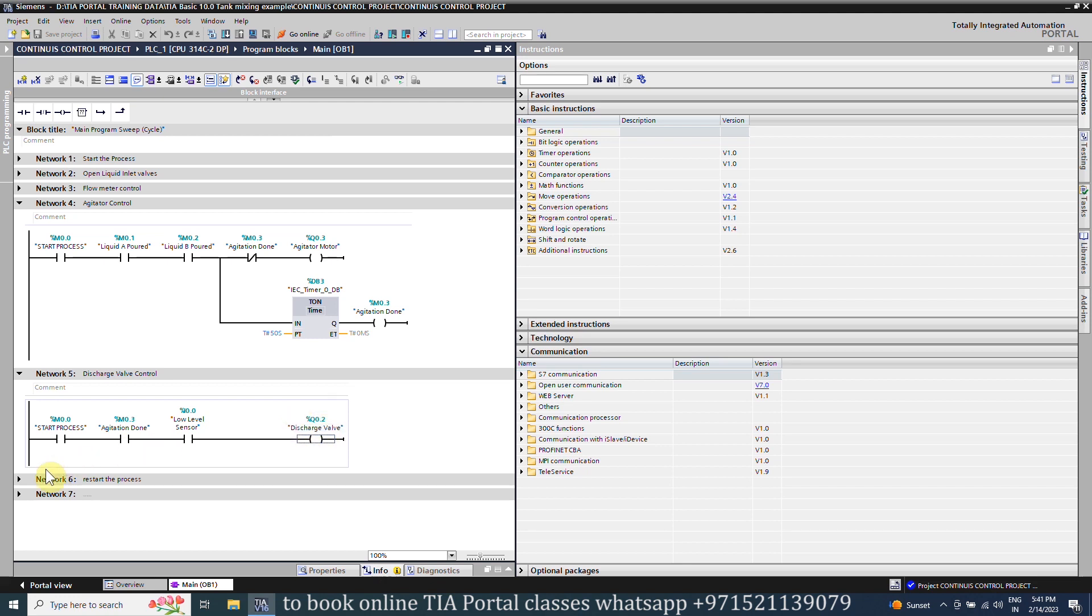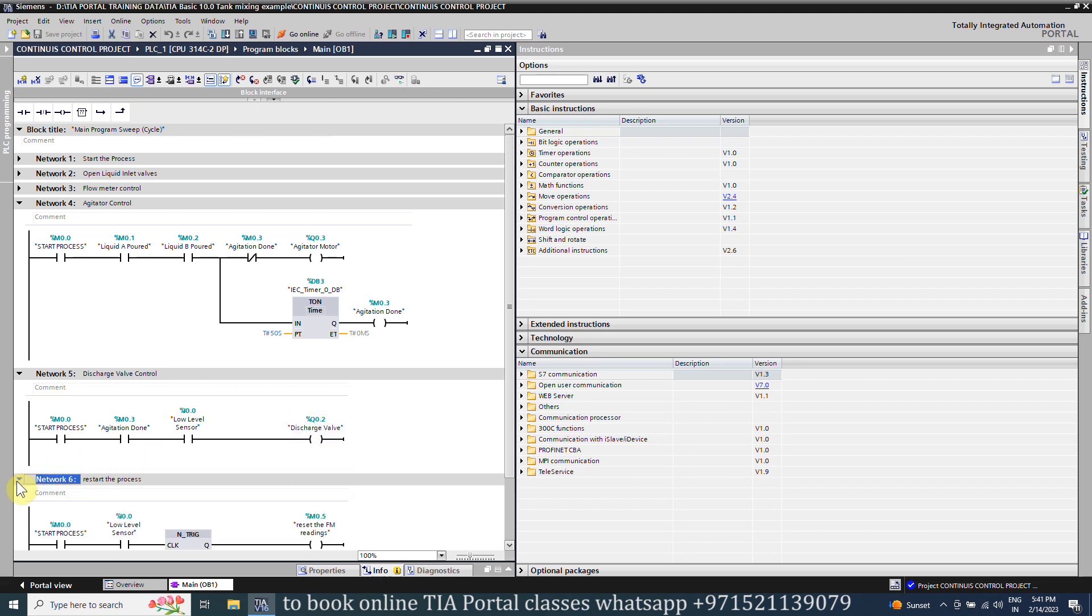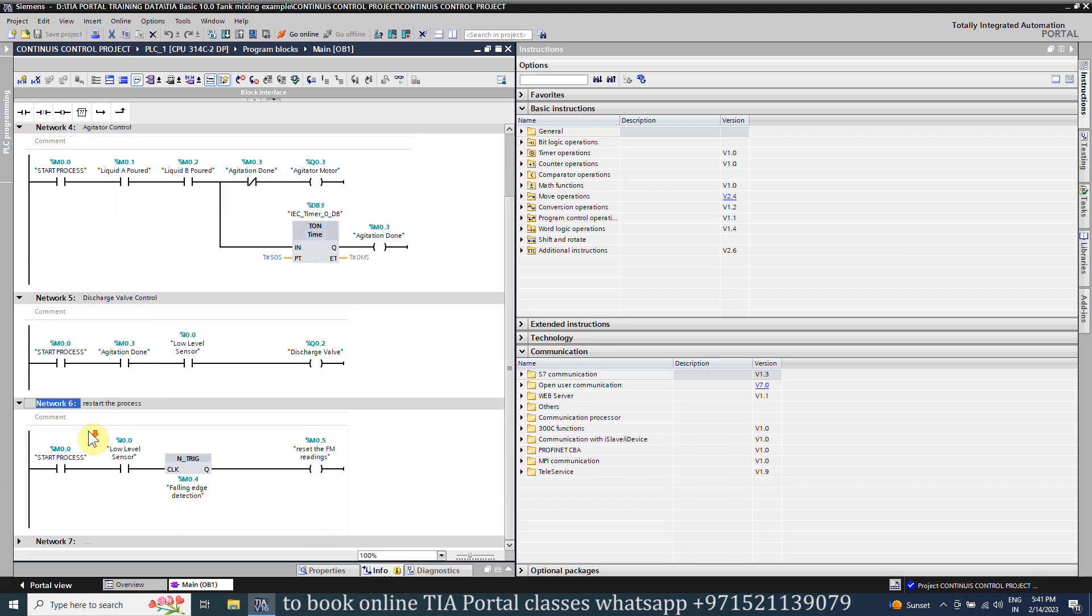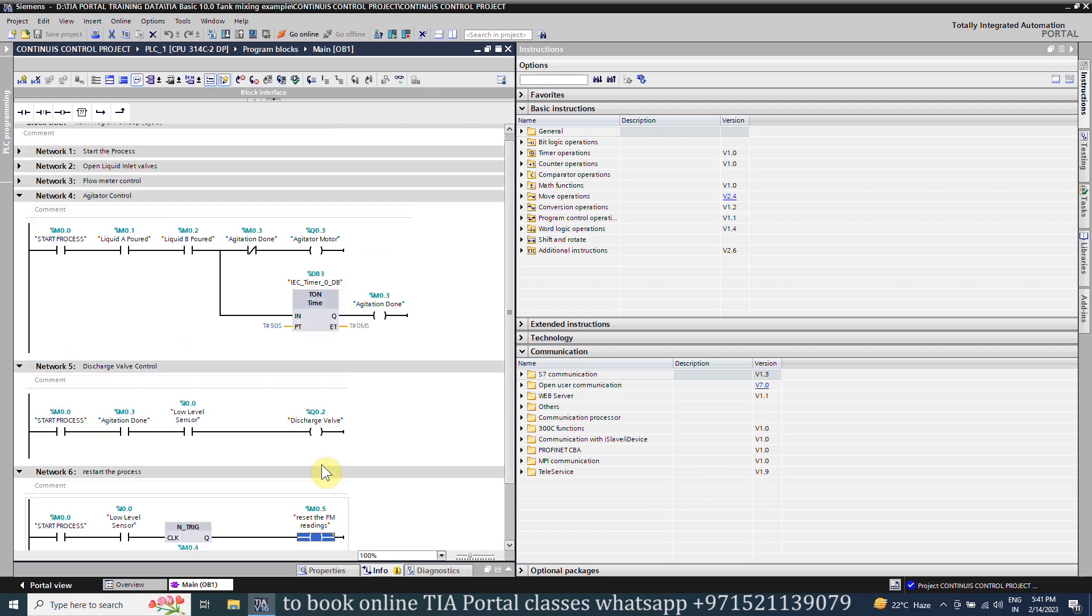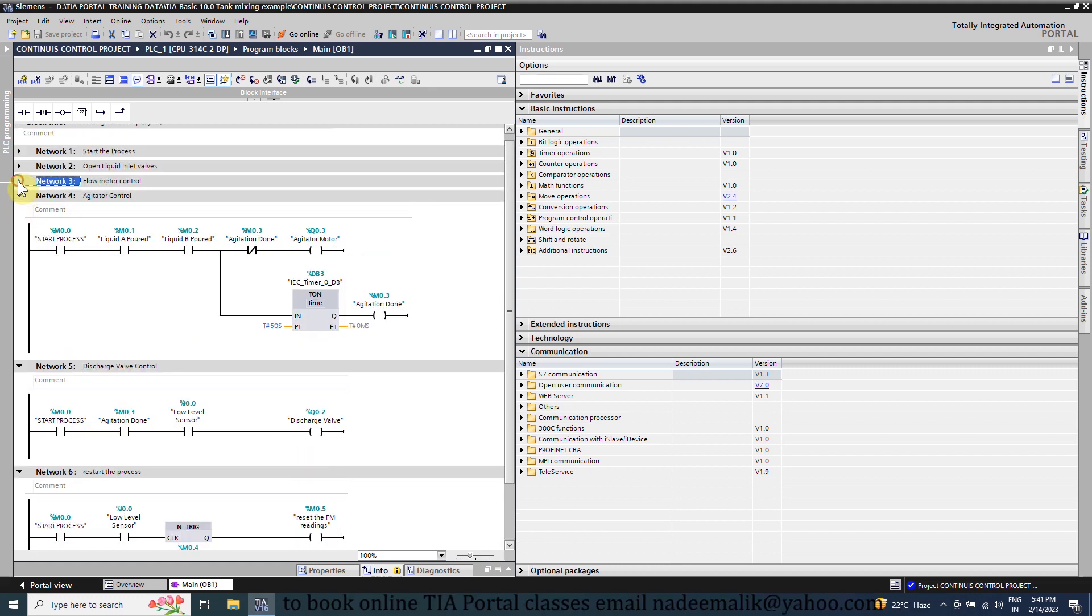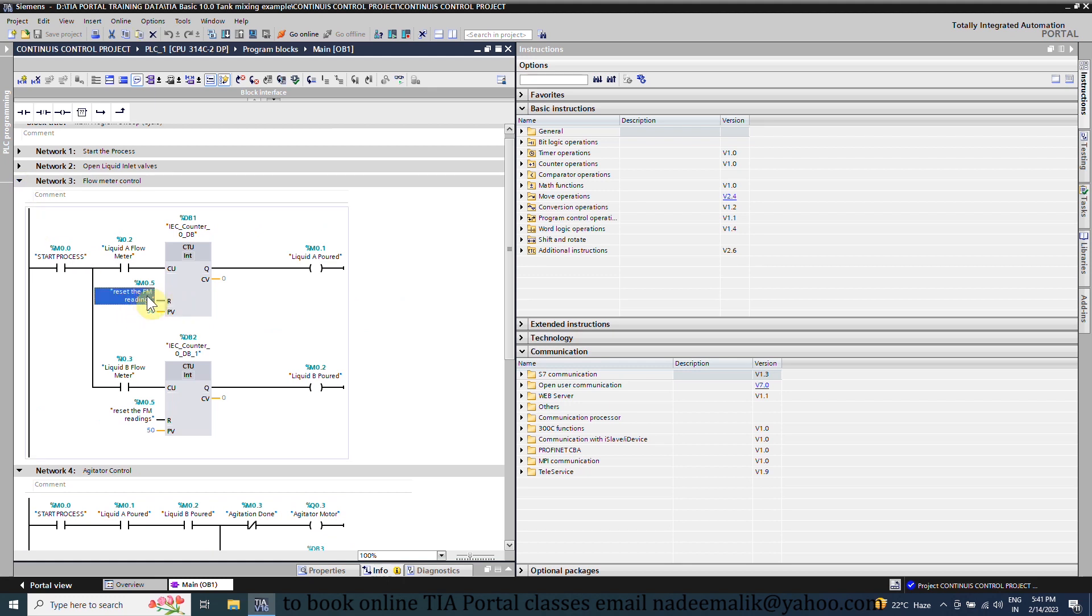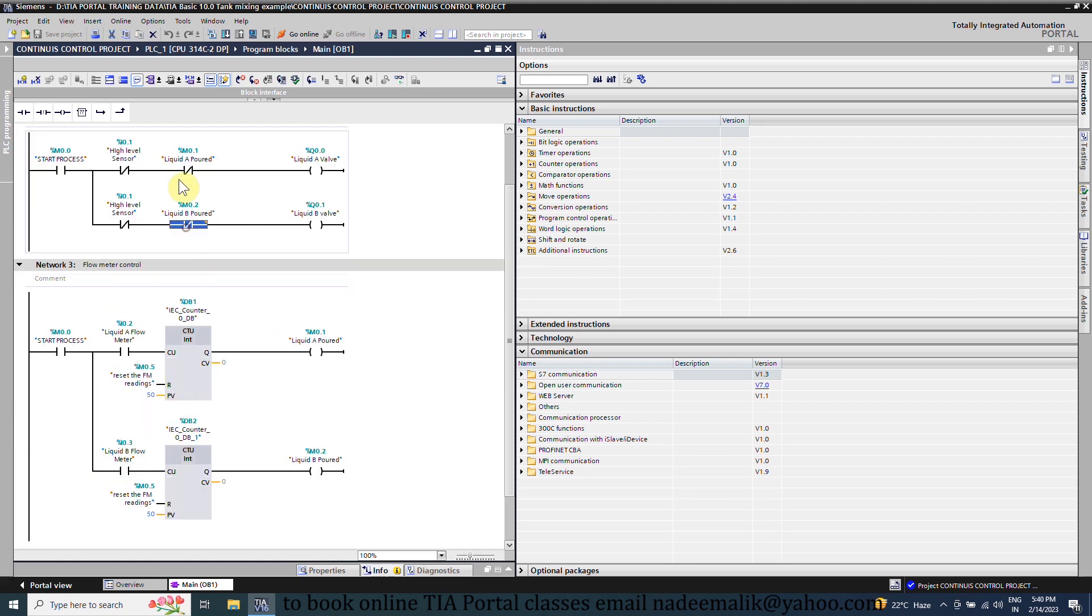In network number six we have a logic to restart the process and fill the tank again. As the water level falls below the low level probe I0.0, this contact opens. And on the negative edge the reset flow meter bit M0.5 turns on for one PLC scan cycle. This bit will reset the current values of both counters back to zero, and this will open both inlet valves again to start filling the tank.